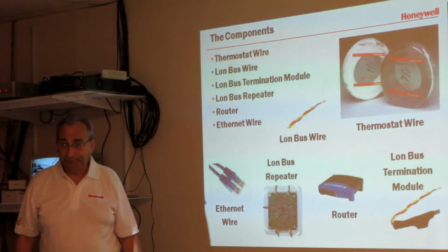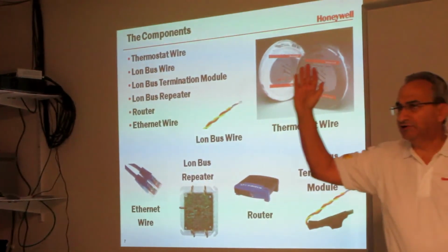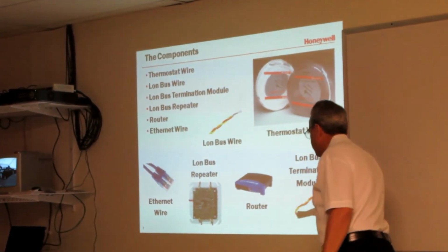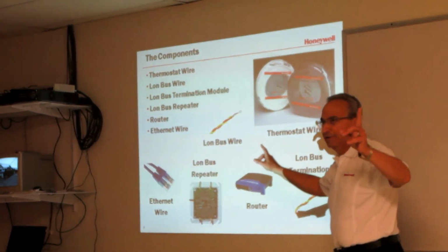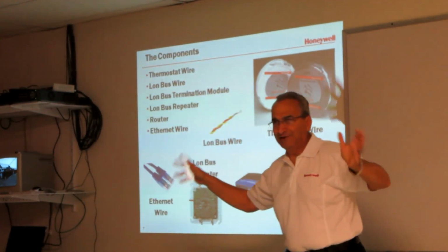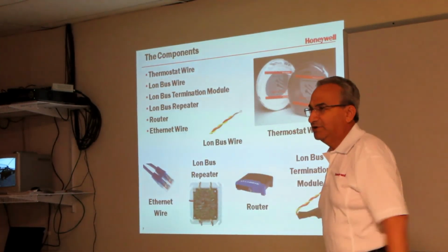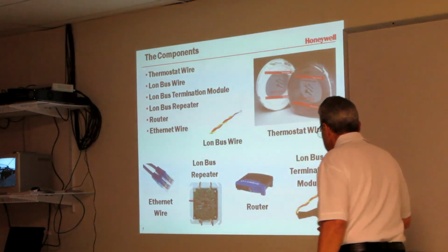And your termination module, this is a very important thing. How many here work with LON already? LON devices. Okay, we've got a couple of you already. So you know about the termination module. If you don't have this on each end of the bus, you'll get device online, device offline, you get communication errors. This drives you nuts. A lot of alarms for no reason.